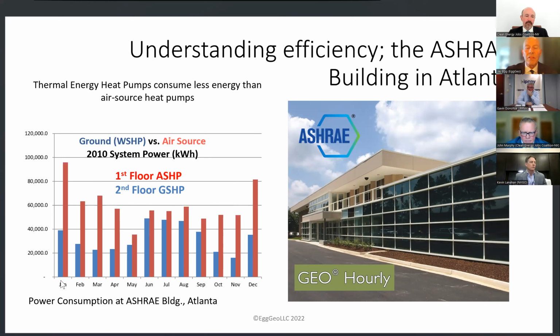If you look at these months—January, February, March, October, November, December—why are the air source heat pumps using so much more demand for electricity per square foot than the geothermal? The answer is simple: heat transfer and fluid flow. The ground is 55 or more degrees year round, so you get incredibly improved performance.